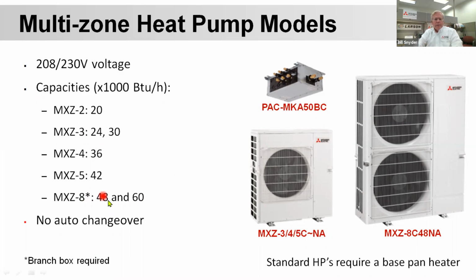So that's the standard heat pump, and that requires a base pan heater. But keep in mind that if you're doing the 4 and 5 ton unit and the standard unit, you do have to have a branch box. Now the branch box can make it easier, or it can make it more difficult. Just be aware that there are 2 pipes, a high and a low side, almost like a suction and liquid line, that run from the branch box to the outdoor unit.